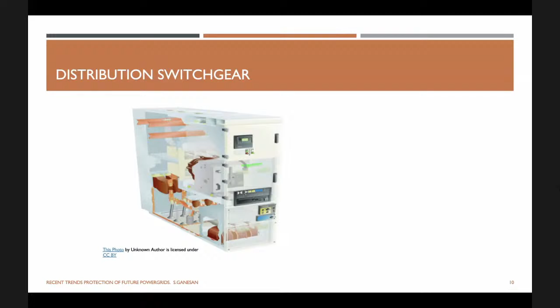Now, where is protection going? All along, for almost a century I would say, protections have been reactive. They sense currents, voltages, frequencies, or whatever you may name. They continuously monitor them, and if things go wrong, then they do some action. But moving forward, we are possibly getting into an age when we are able to process this information thanks to a highway, typically a digital highway, to the last equipment in the switchyard, right to the isolator I would say.